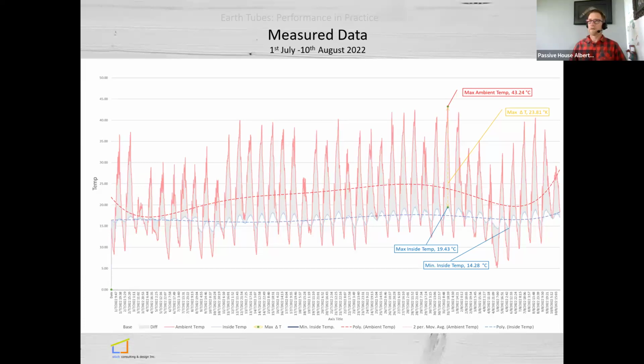Yeah, and as far as I've been able to find, none of the lower cost HVI certified HRVs or ERVs have that bypass option. It's only once you go to the Passive House certified ones that you get that summer bypass, which I think is becoming a pretty good advantage, because you get to use it for pre-cooling, especially on an earth tube.